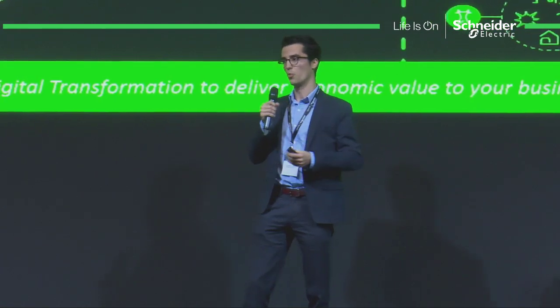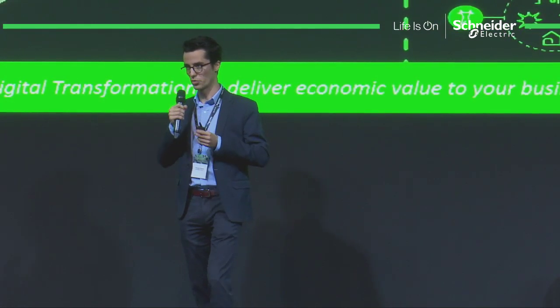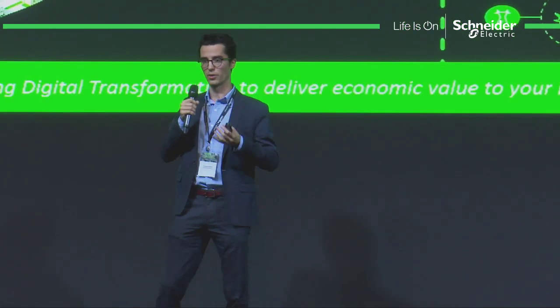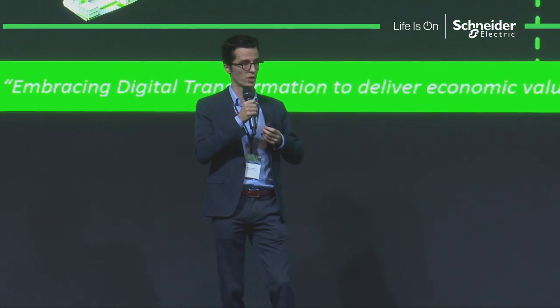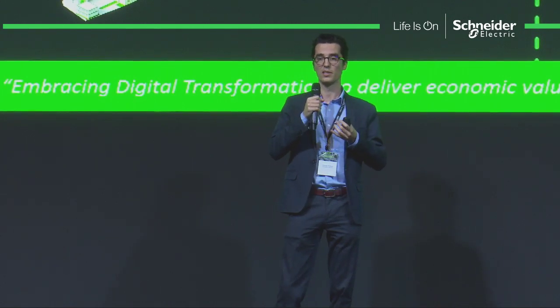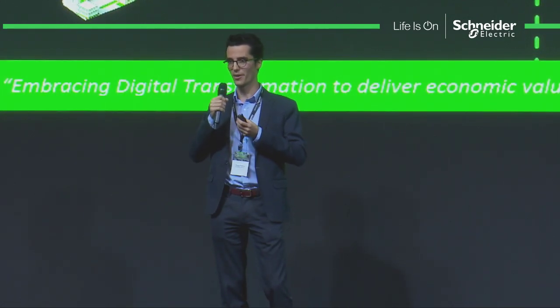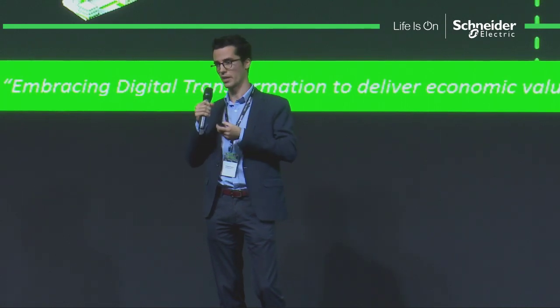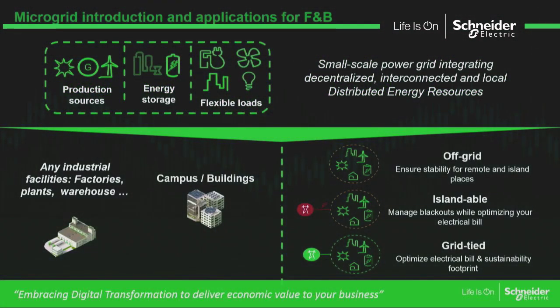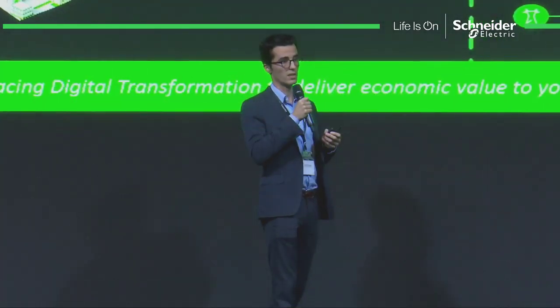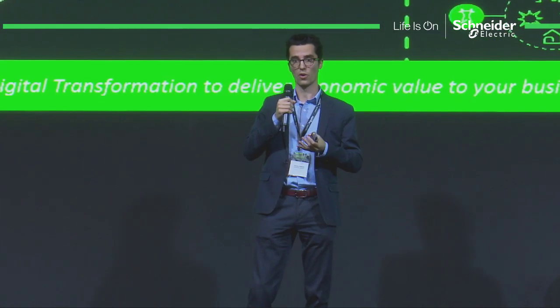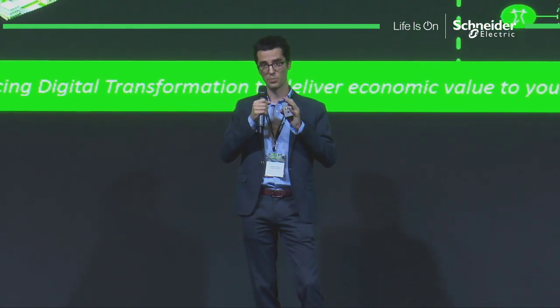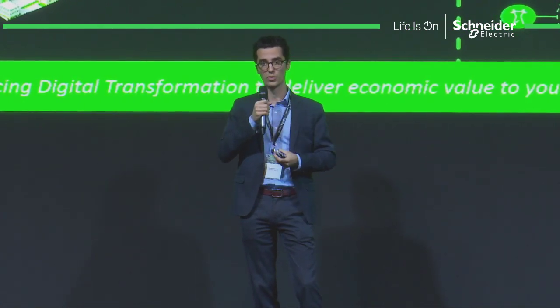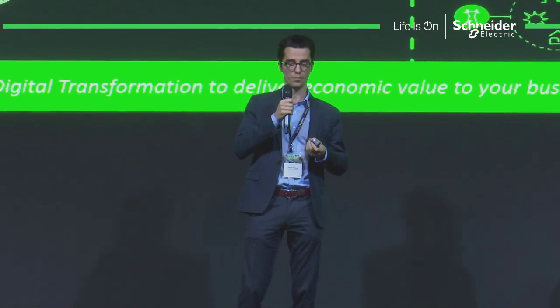And in between the two, we apply this technology for the so-called islandable microgrid. This would mainly be for facilities located in places where the grid exists but may not be very reliable. So in normal conditions, you generate some electricity locally and import the rest from the grid. But in case of a grid outage, we have the ability to automatically disconnect your factory or site from the grid and keep running the most critical loads using the available local generation.